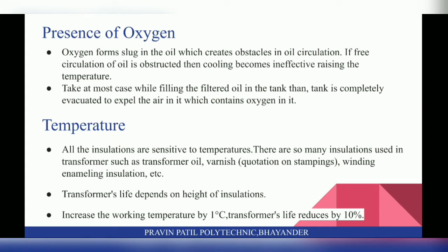Next is Temperature. All insulations are sensitive to temperature. There are many insulations used in a transformer such as transformer oil, varnish, winding, enamelling, insulation etc. A transformer's life depends on the health of insulations. If the working temperature increases by 1 degree Celsius, the transformer's life reduces by 10%. So temperature is also a main factor.